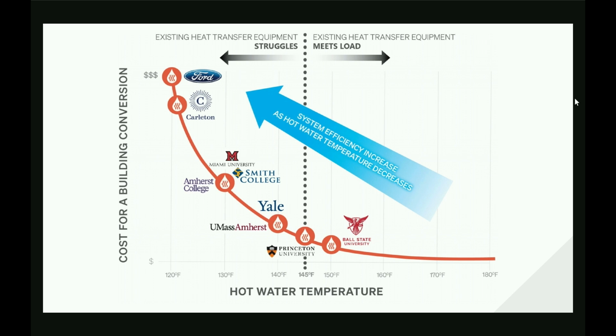Miami University chose to go to 130. They ended up spending about $400,000 on building conversions because their buildings could handle that reset water temperature without doing much. Princeton, with a lot of legacy buildings that are old, found out they could run at 145 without doing a whole lot. So this is the key to finding the right water temperature without spending major money converting your buildings.